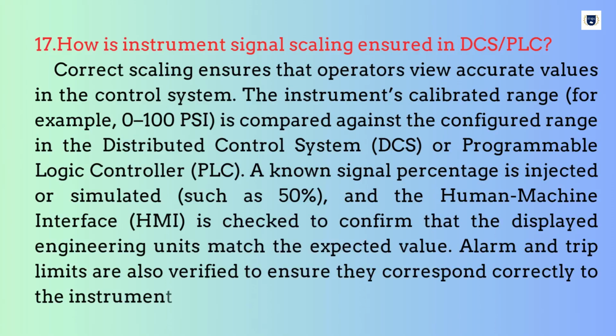How is instrument signal scaling ensured in DCS PLC? Correct scaling ensures that operators view accurate values in the control system. The instrument's calibrated range, for example, 0 to 100 psi, is compared against the configured range in the distributed control system, DCS, or programmable logic controller, PLC. A known signal percentage is injected or simulated, such as 50%, and the human-machine interface, HMI, is checked to confirm that the displayed engineering units match the expected value. Alarm and trip limits are also verified to ensure they correspond correctly to the instrument's operating range.